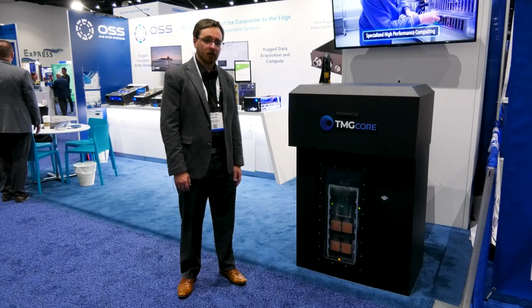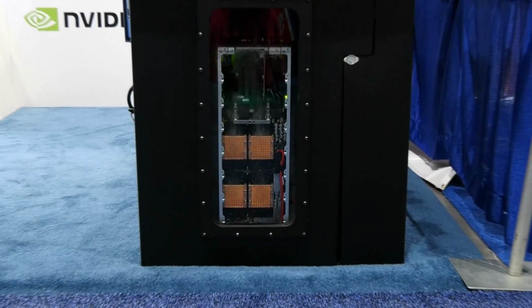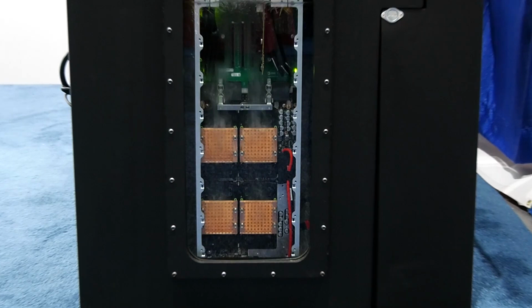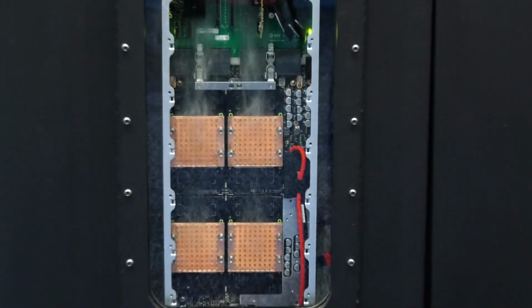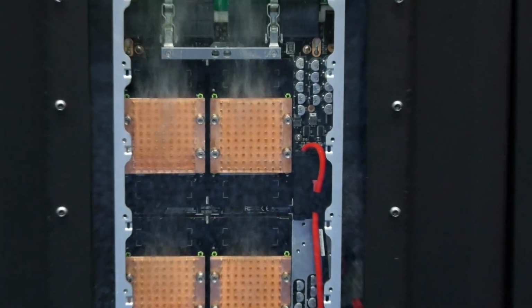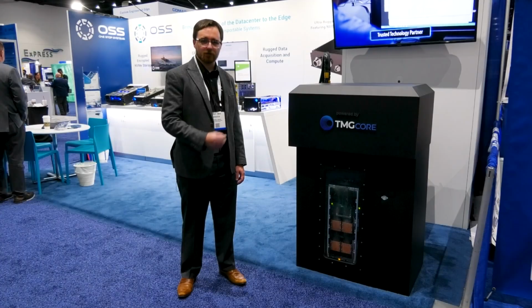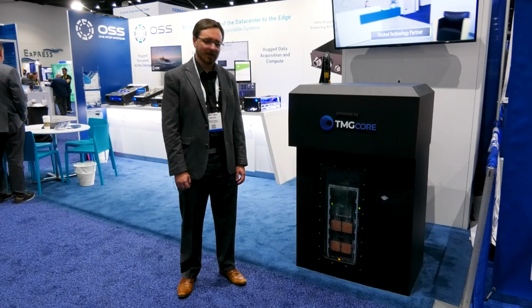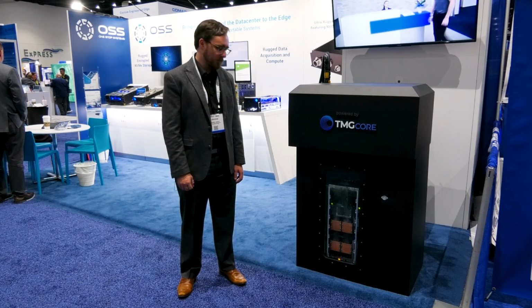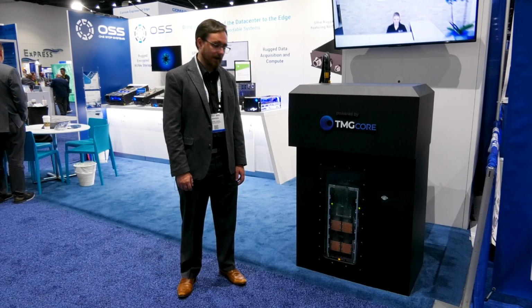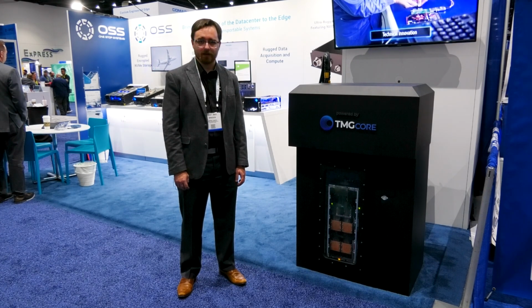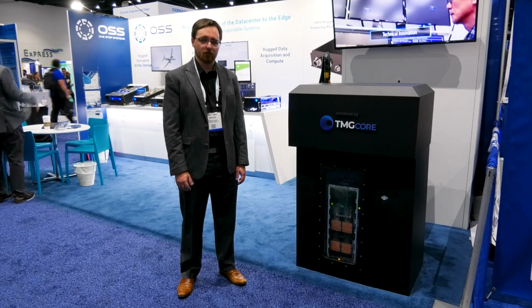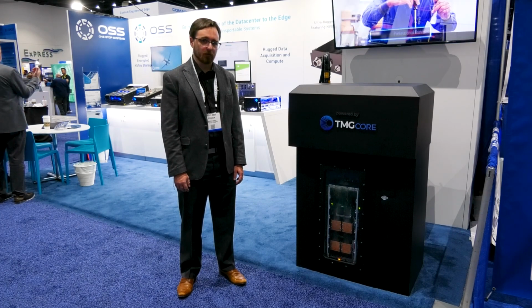What we're showcasing here is a two-phase immersion cooled system. We're taking advantage of the latent heat properties of the fluid to actually boil the fluid on the heat generating components of Rigel, pull that heat to the surface, and recirculate it through the fluid condensing on a condensing coil. It's an extremely thermally efficient design, which allows you to operate at an ambient temperature far beyond what you could do through air cooling or even a direct-to-chip liquid cooling approach.